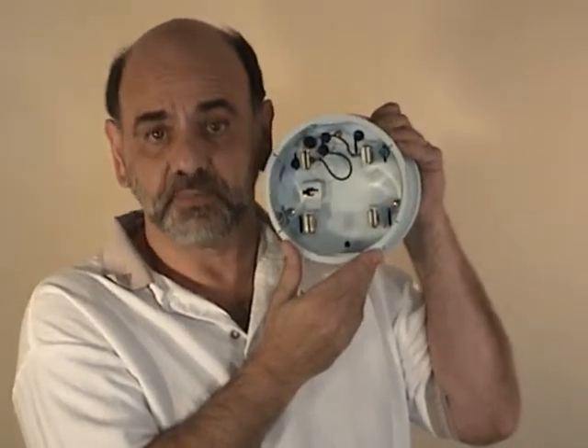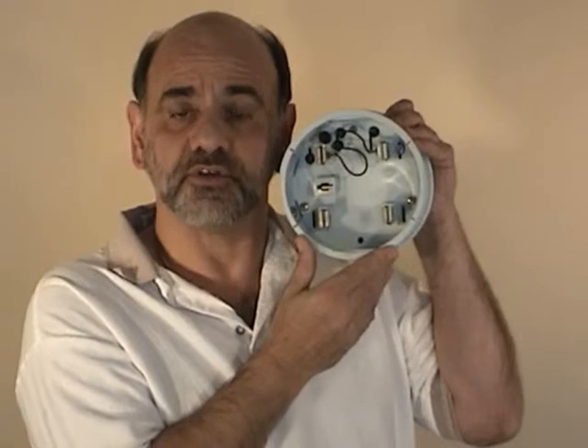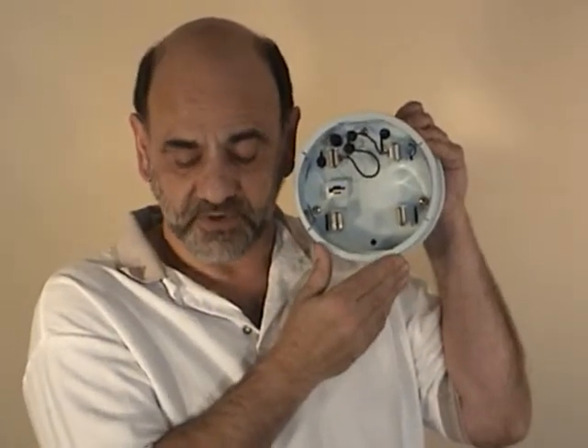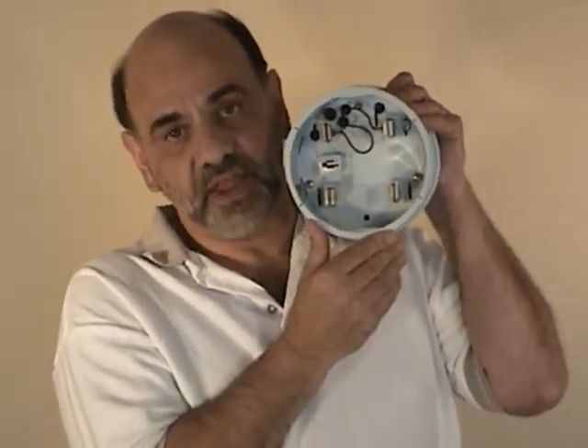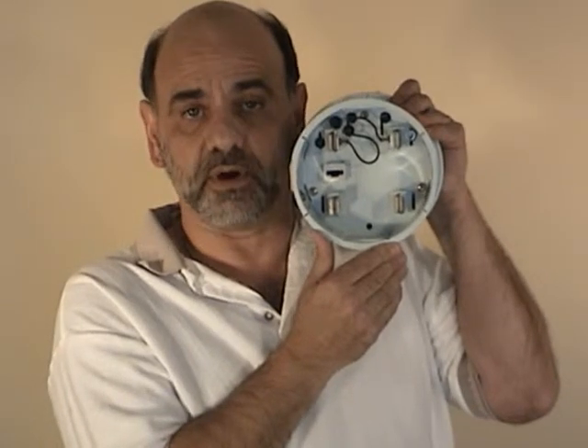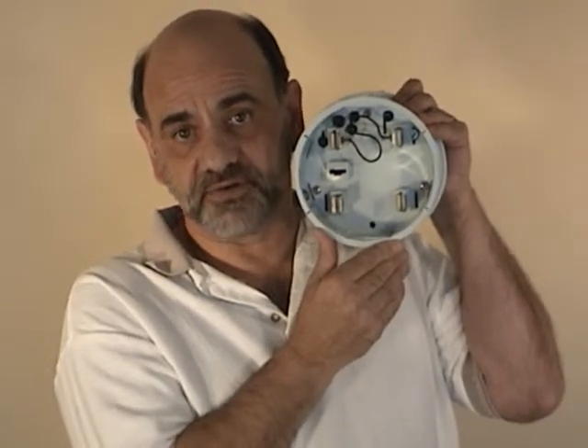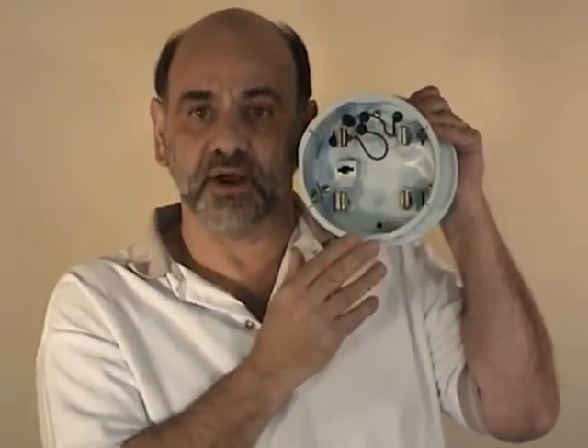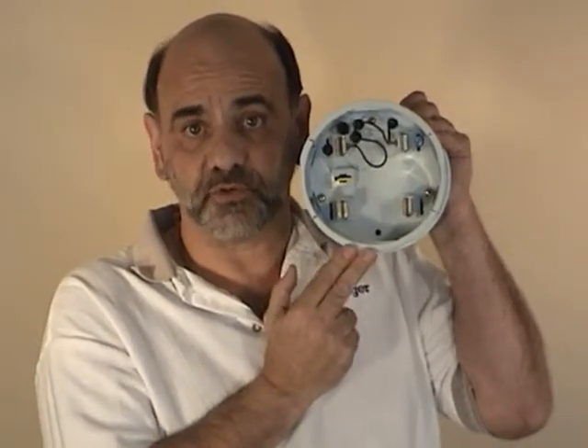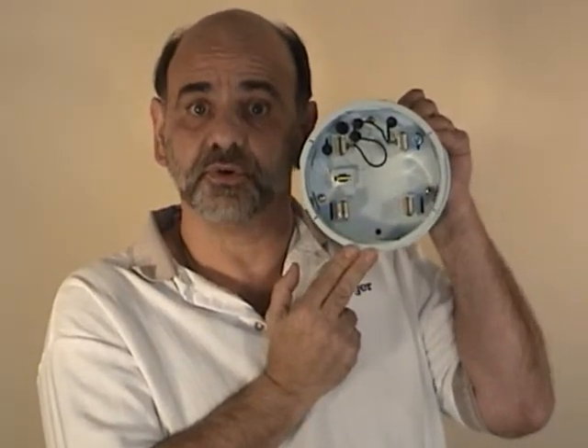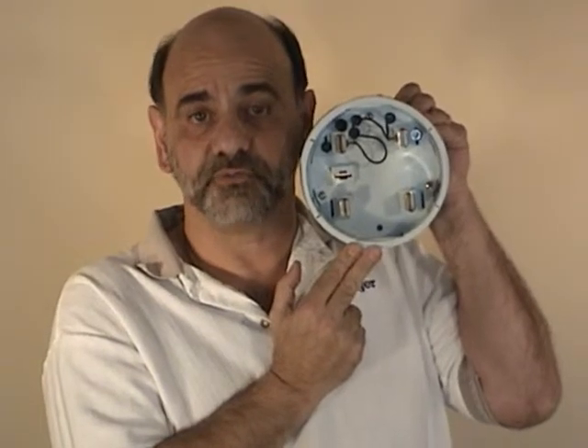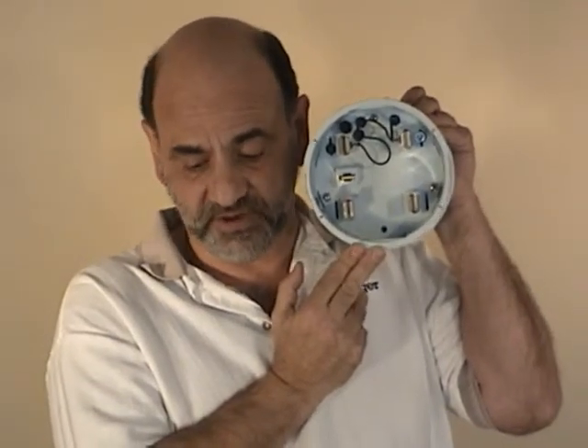The first setup is a standard setup that records all 5 of those parameters. The second setup is a standard setup, but it also includes power, watts, VARs, power factor, and kVA. The third setup is the standard setup of 3 voltages and 2 currents, but it also includes harmonics on both the voltage channels and the current channels.